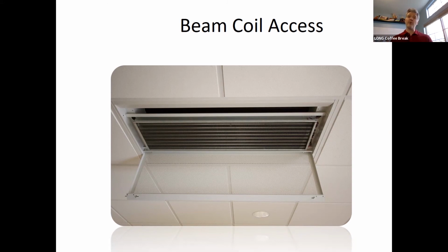I actually have one particular project where we did install a mesh filter on the inlet of that, and those have since been removed because they found out years later that they were completely clean, and why have it in there? You'll gain some capacity back and have less maintenance by not having that device there.